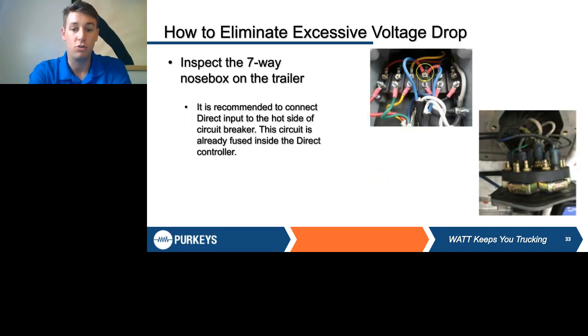Third, you can go to the trailer side and inspect the 7-way on the trailer. Our system is a 20 amp DC-DC converter, so we need a 30 amp circuit in there. You want to check the circuit breakers in your 7-way nose box and make sure they are 30 amp circuit breakers.